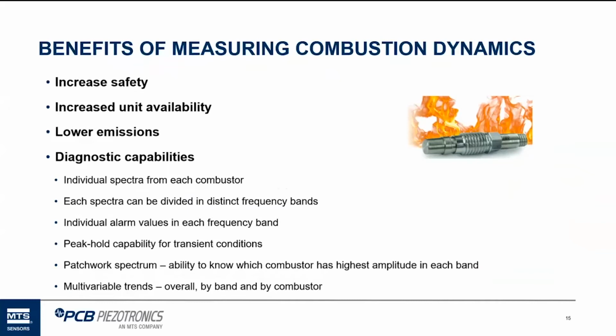So, the benefits of measuring combustion dynamics: it keeps your unit safer. If you don't have that information and there's a problem, it could cause an event that's dangerous to the plant and plant personnel. You can run your turbine longer and make it more available, if it's a peaker type of plant, so it can run when necessary if you're monitoring combustion dynamics properly.